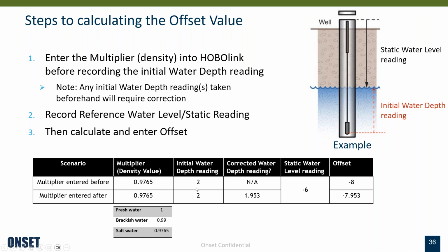That initial reading reports back 2 meters. So at that point, to set up your offset, what you need to do is, I guess it's adding, but it's more like subtracting. Because you want to take that initial static water level reading, which is -6. Again, it's below the reference point, so you want to look at it as a negative value, and then subtract the 2. So from the sensor to the top it will be 6, and you add the 2, it's 8. So that offset comes out as -8, so that in the equation it does 2 minus 8, which gives you -6. Kind of funky, but that's the best way I can explain it.